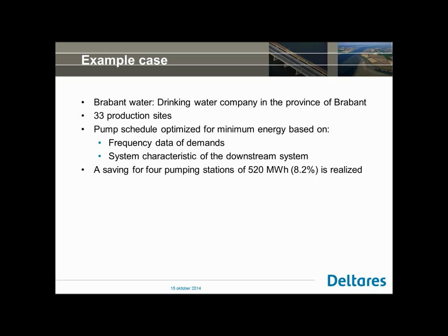To show you that this really works, we did some work together with Brabant Water. Brabant Water is the drinking water company in the province of Brabant in the Netherlands. They have about 33 production sites where they produce water and supply it to the networks. They started optimizing the pump schedule based on frequency data of demand — they know what the demand series are — and the system characteristics, which you can create with the system characteristic module as I just showed you. Based on this data, for each pumping station they optimized the energy usage. At the end they saved 520 megawatt hours, which is about 8% of their total power usage — a nice improvement.